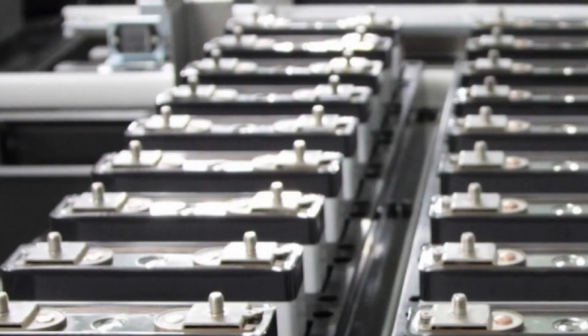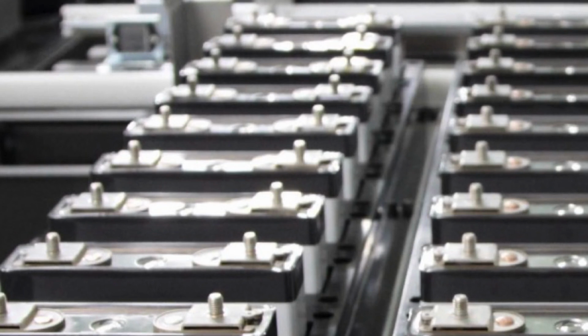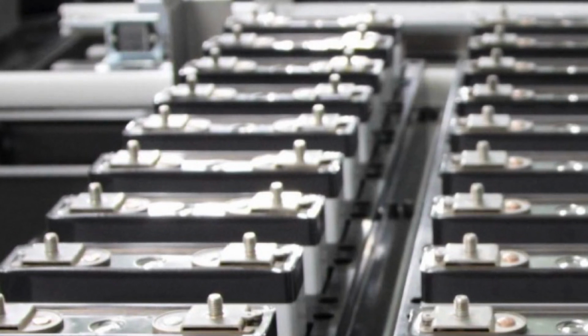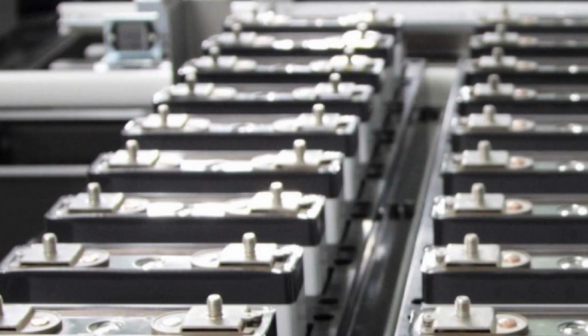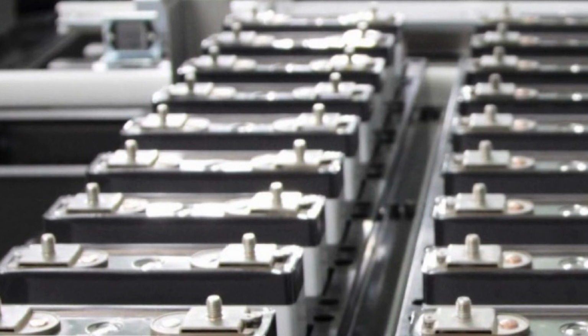So central battery emergency lighting is fairly prevalent within data centres. This tends to be used for the multi-tenanted lease spaces, because they are constructed in one go, and therefore the batteries and the battery system, and the lighting linked to it, is all built and installed in one go. With the owner-operators, they tend to have that phased construction, so it's very difficult to construct a central battery-operated lighting system when the system is phased.